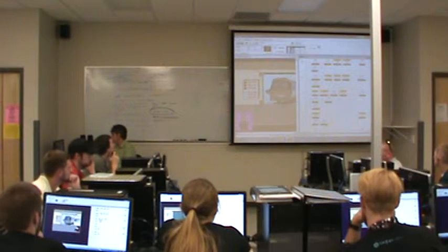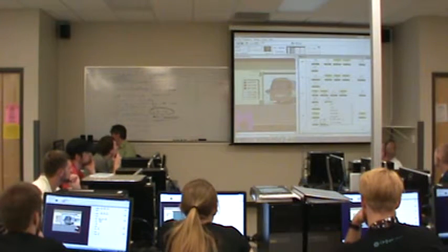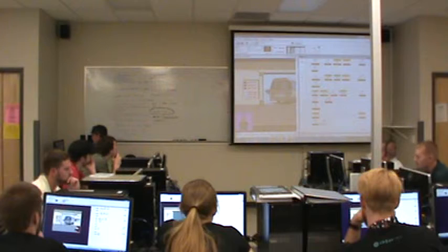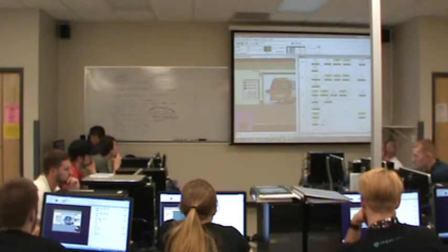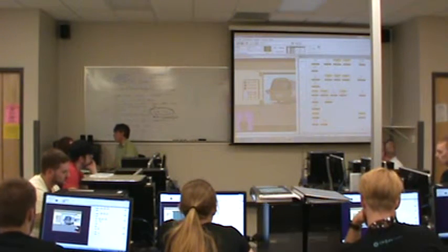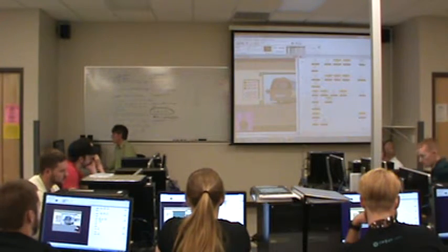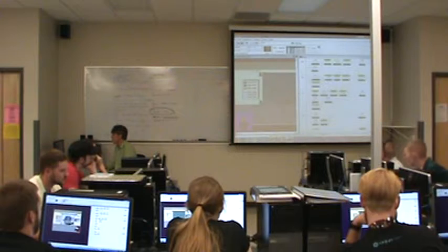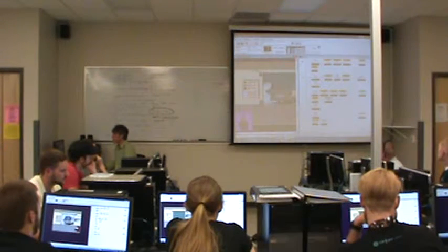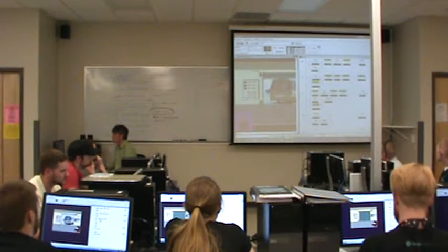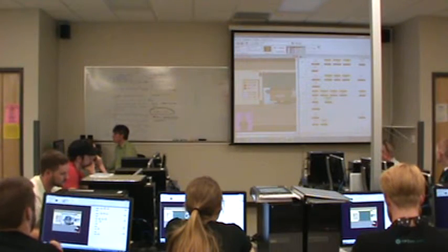Okay. So this would be actually the slow flash. Bit 8, because bit 8 is above bit 7, bit 7 will be the fast flash. So download, run, open, close. You see that ajar is flashing at twice the rate of either open or shut. If I stop in between, the ajar stays on.